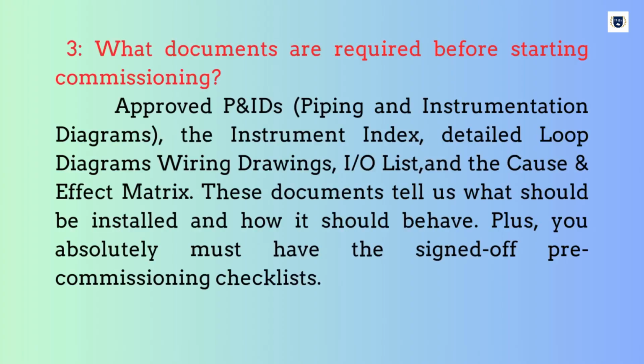What documents are required before starting commissioning? Approved piping and instrumentation diagrams, the instrument index, detailed loop diagrams, wiring drawings, I/O list, and the cause and effect matrix. These documents tell us what should be installed and how it should behave. Plus, you absolutely must have the signed-off pre-commissioning checklists.